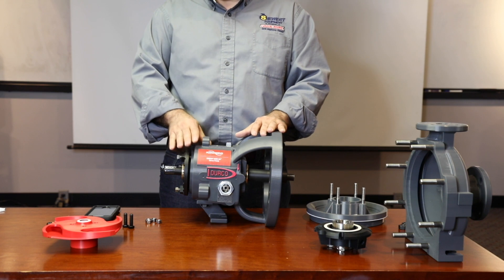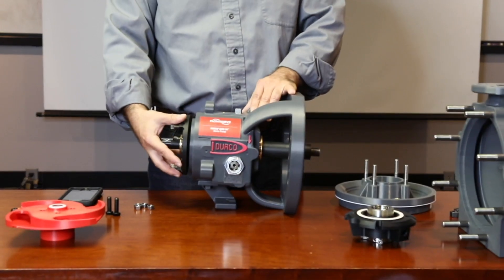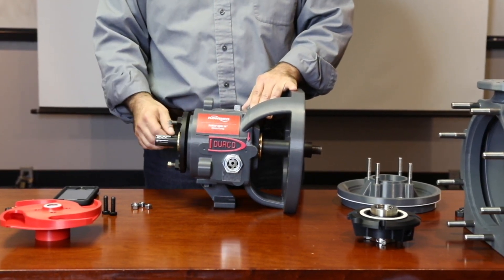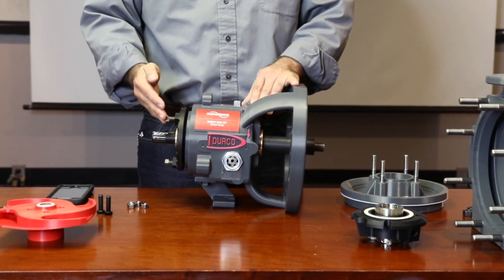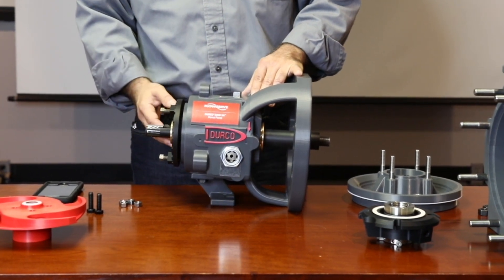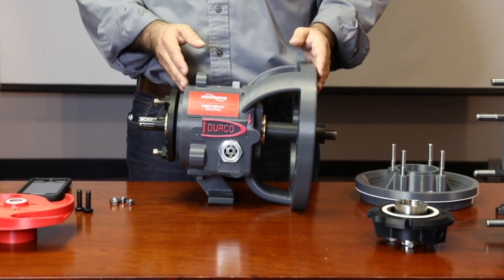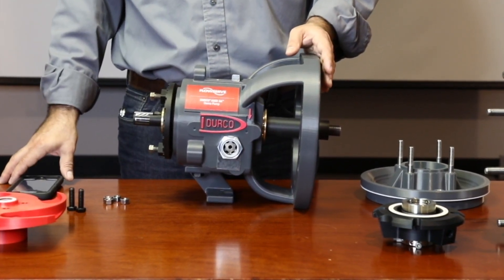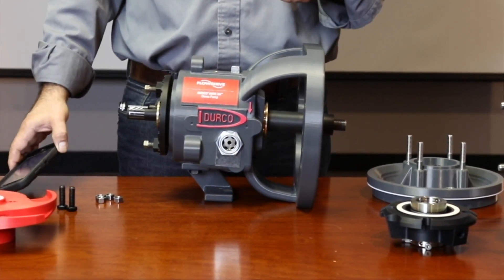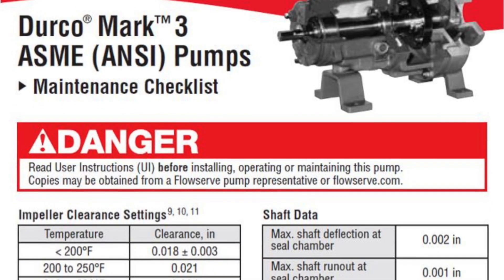As I reassemble the pump, I will explain some of the advantages of the Durco over competitor pumps. Unlike some competitors' pumps, the Durco uses an adjustment micrometer plate with three jam bolts that are not used to move the adjustment plate, but only to lock it in place. To reestablish the proper impeller clearance, you'll need to know the operating conditions of your pump. Refer to the Durco manual and the impeller clearance chart to obtain those values.